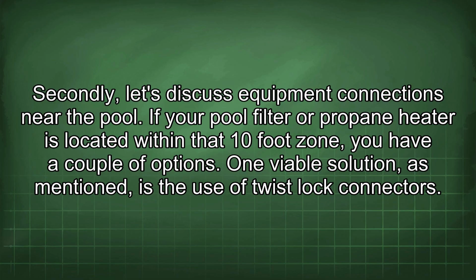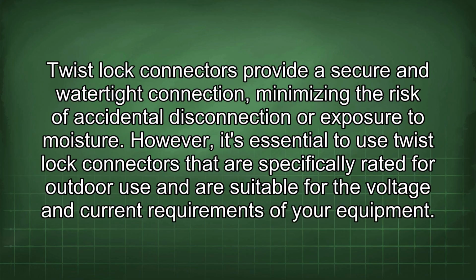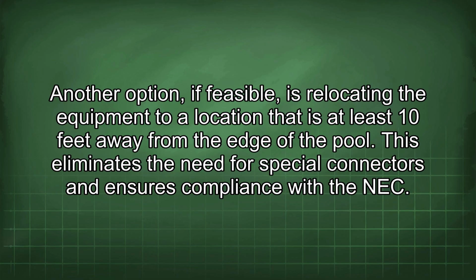Secondly, let's discuss equipment connections near the pool. If your pool filter or propane heater is located within that 10-foot zone, you have a couple of options. One viable solution, as mentioned, is the use of twist lock connectors. Twist lock connectors provide a secure and watertight connection, minimizing the risk of accidental disconnection or exposure to moisture. However, it's essential to use twist lock connectors that are specifically rated for outdoor use and are suitable for the voltage and current requirements of your equipment. Another option, if feasible, is relocating the equipment to a location that is at least 10 feet away from the edge of the pool. This eliminates the need for special connectors and ensures compliance with the NEC.